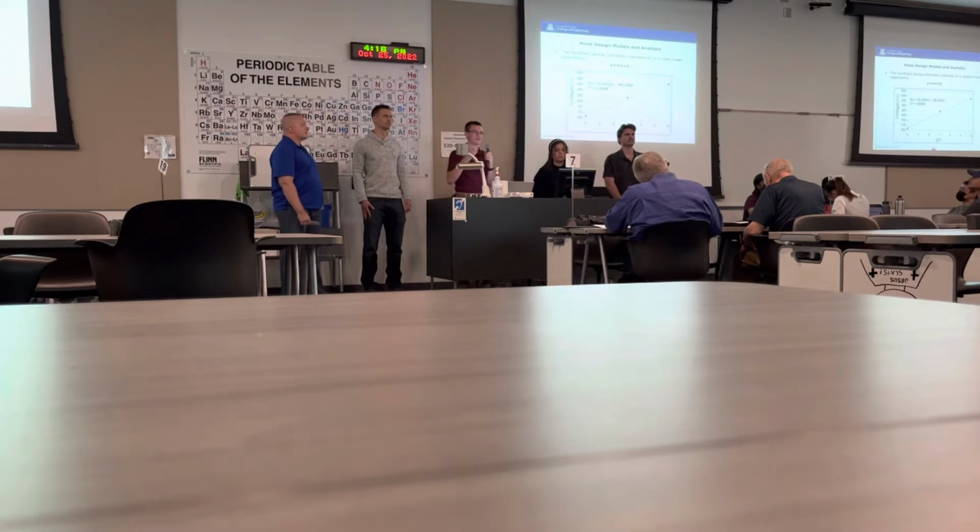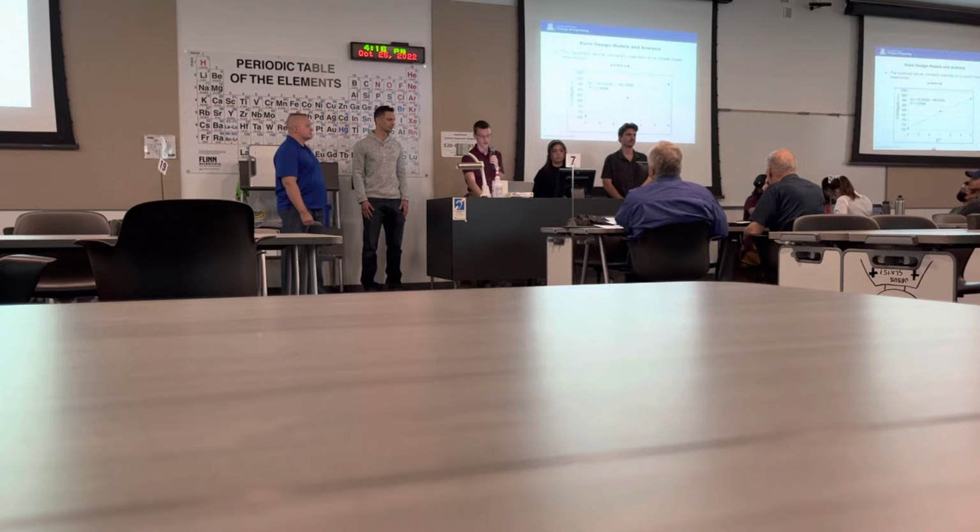So, some models and analysis that we can apply to this system. Ultimately, this device will rely on a simple linear relationship, y = mx + b, for pH and calcium. All the ISEs rely on this linear relationship, which we will have to calibrate and find for ourselves.